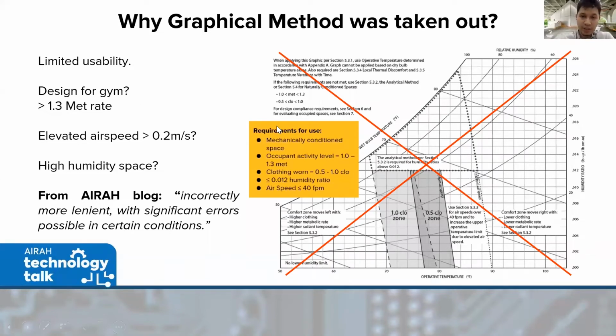As you see here, the requirement for use is a mechanically conditioned space—so if you want to design a space without HVAC, you can't use this. Occupant activity level from 1 to 1.3 met, so again it's for an office space; if you want to design for gyms, for example, you can't use this. Clothing worn is 0.5 to 1 clo, again about office space as well.